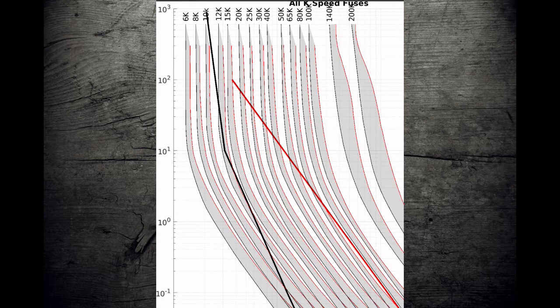Now, if you find yourself in a situation where you have to make a decision, none of the options are grand, right? There is no perfect answer, and now a compromise has to be made. It is preferable that you take the larger of the two fuses and accept your exposure here rather than risking a nuisance trip here.